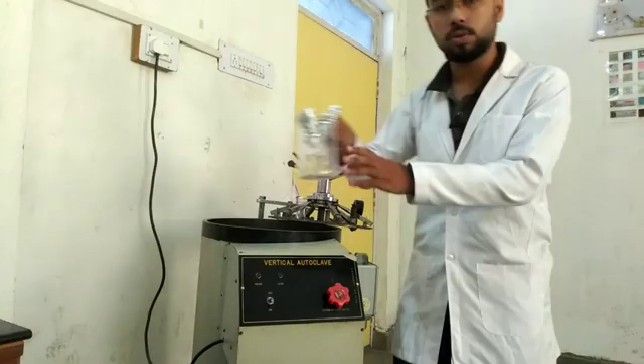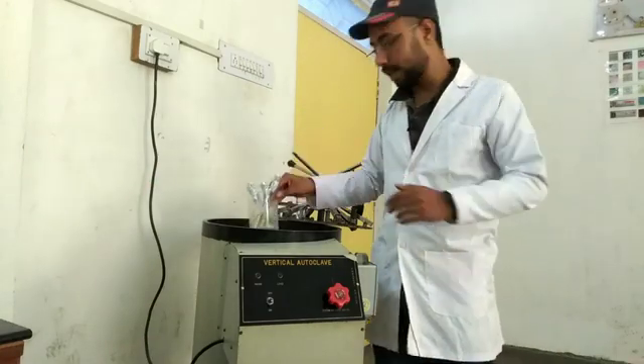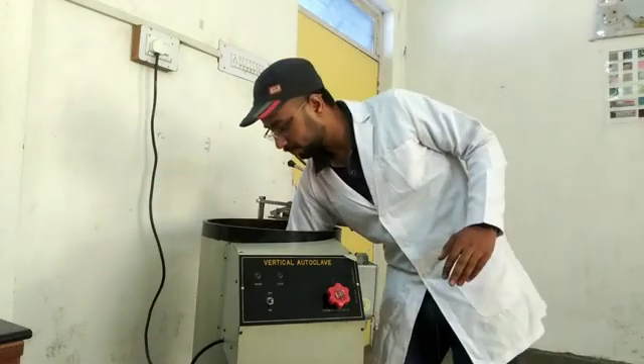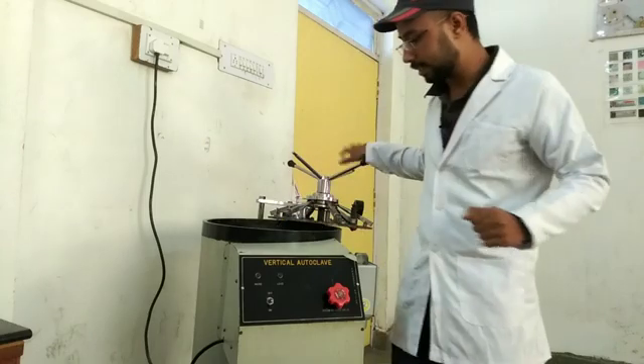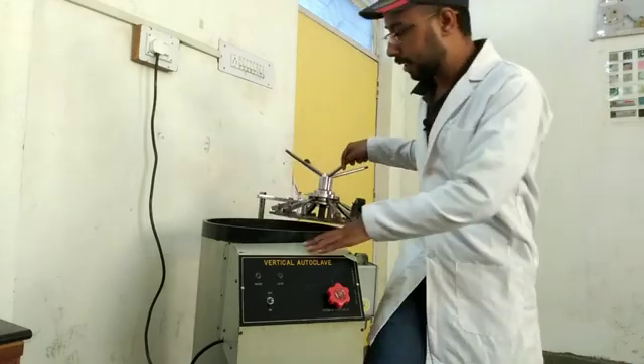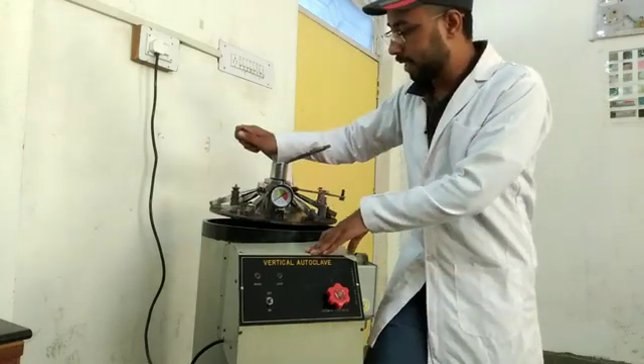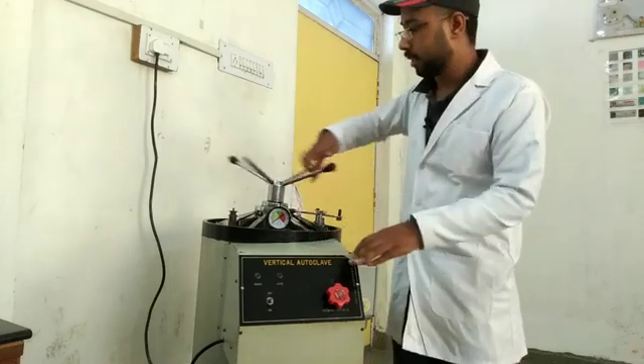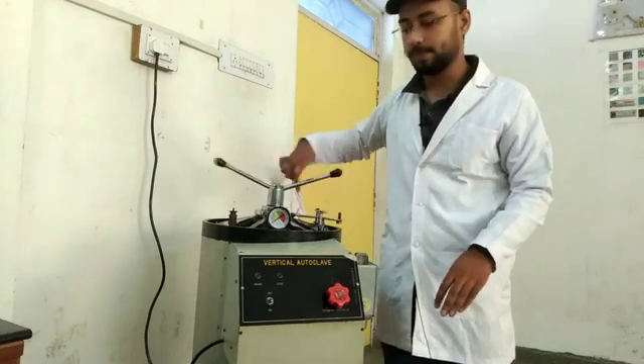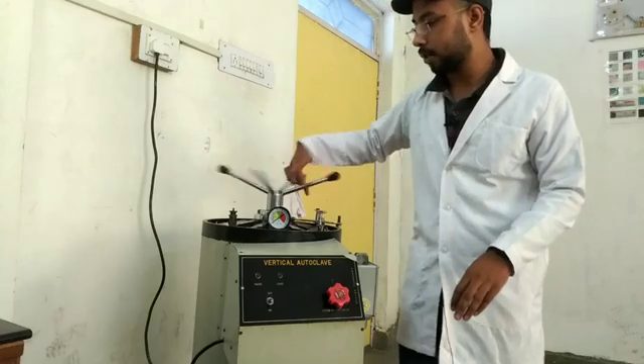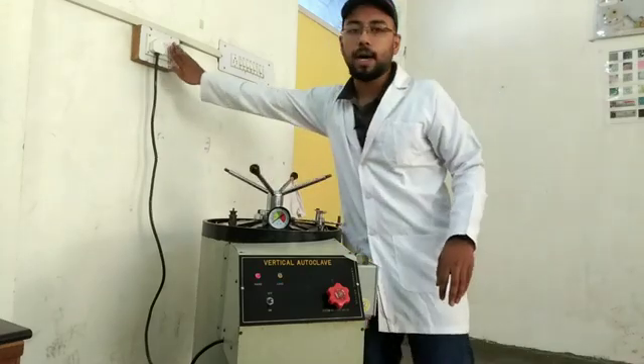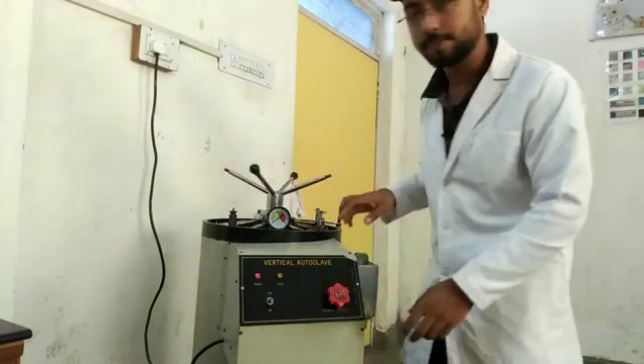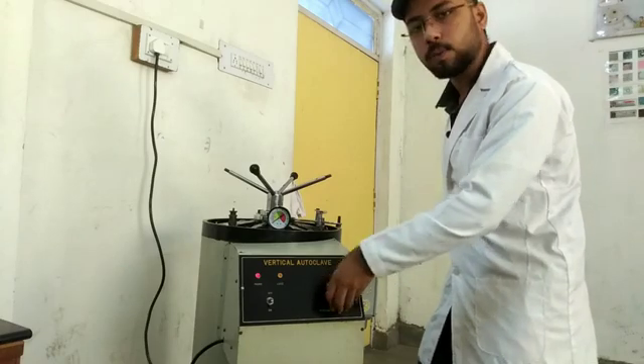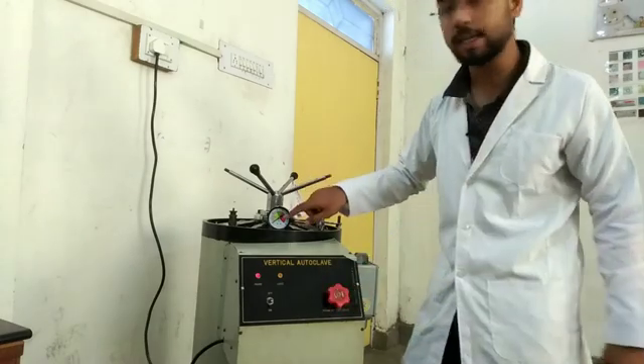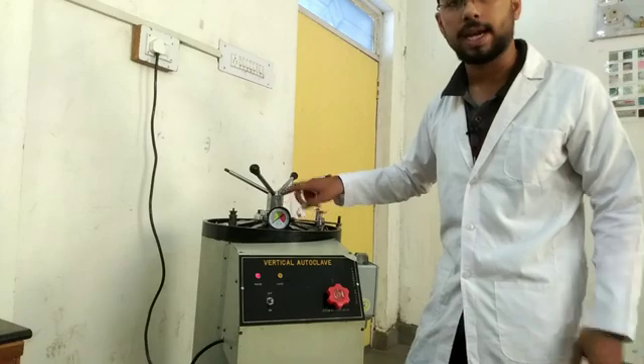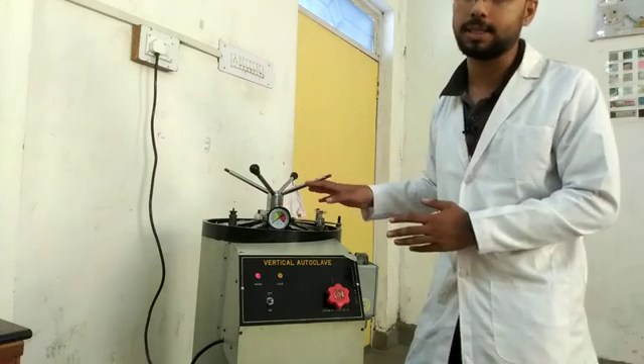Now I just have to put this inside the autoclave, and after that put on the lid. This is the autoclaving procedure. Now I have to turn on the autoclave and close the valve, and wait until it reaches 15 psi, and then 15 minutes for sterilization.